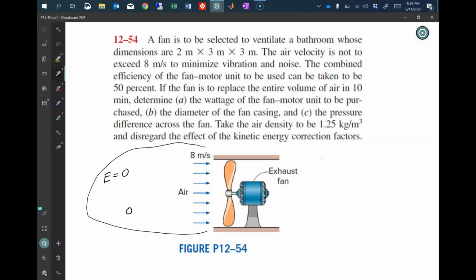Now, the air comes into the duct, and when it comes into the duct, it begins to move, so it begins to have some kinetic energy. When it has kinetic energy, it had to get it from somewhere. It can't get it from the gravity. So at this point, the pressure goes down. It gets kinetic energy by robbing the pressure, so there'll be a little bit of a vacuum. It'll be below atmospheric here. And so the energy has changed. Well, it's the same amount of energy, but it's a different form. So I'm going to call that point 1.